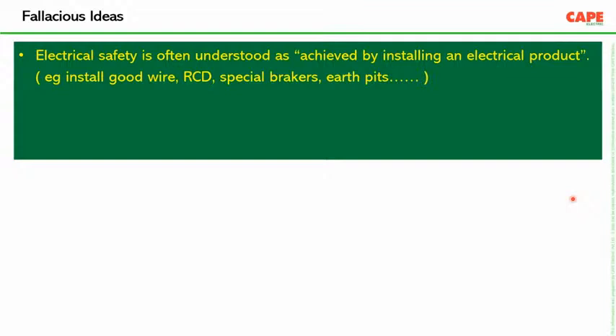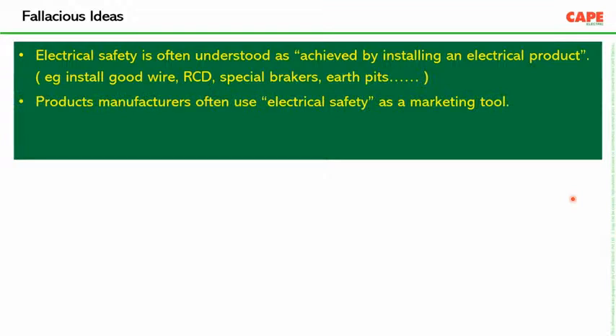Somebody says, no, you install an RCD, you get safety. Somebody says you make a special circuit breaker, you get safety. Somebody says you put 5 more earth pits, you get the safety. Actually, safety has nothing to do with these components. Safety has something to do with the whole installation. Your installation should follow the basic safety rules. As I said, if I ask an engineer, what kind of network are you following? Are you following TT system, TN-S system, TN-C-S system? There the confusion starts.